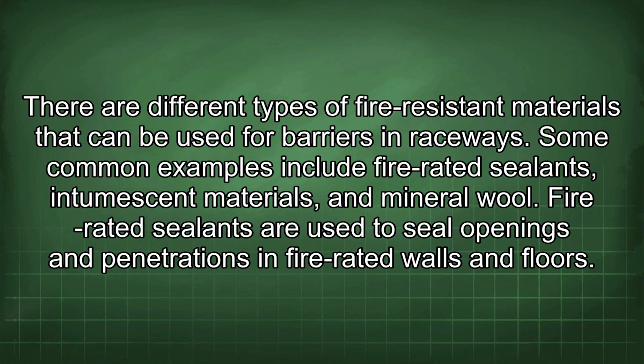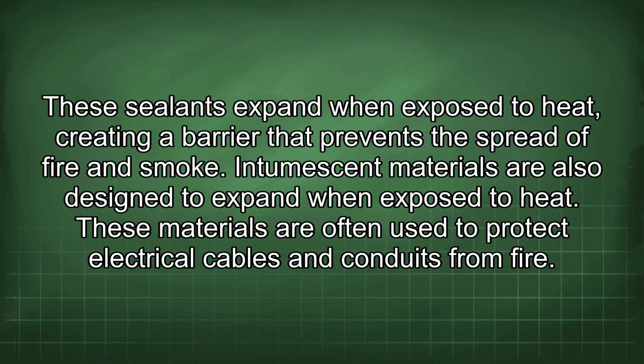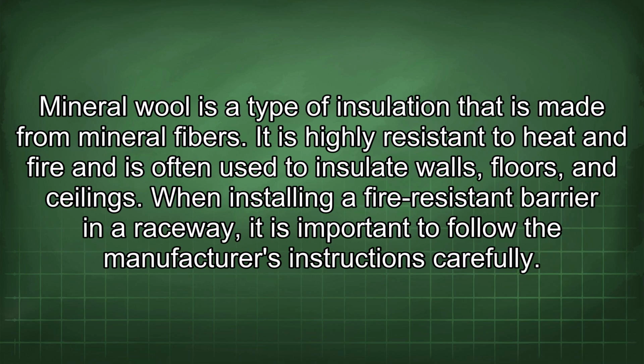Fire-rated sealants are used to seal openings and penetrations in fire-rated walls and floors. These sealants expand when exposed to heat, creating a barrier that prevents the spread of fire and smoke. Intumescent materials are also designed to expand when exposed to heat. These materials are often used to protect electrical cables and conduits from fire. Mineral wool is a type of insulation that is made from mineral fibers. It is highly resistant to heat and fire and is often used to insulate walls, floors, and ceilings.